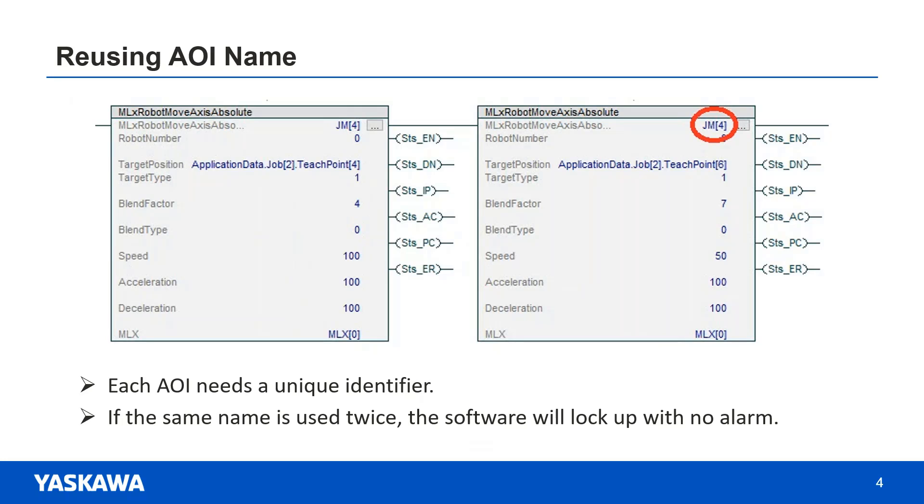Sometimes it seems like it's a mystery why the software is not operating like it should. When this happens, the first thing you should check is whether or not an AOI name has been used more than once. This unique identifier cannot be used anywhere else in the ladder, even if it's on a rung that will never be active.